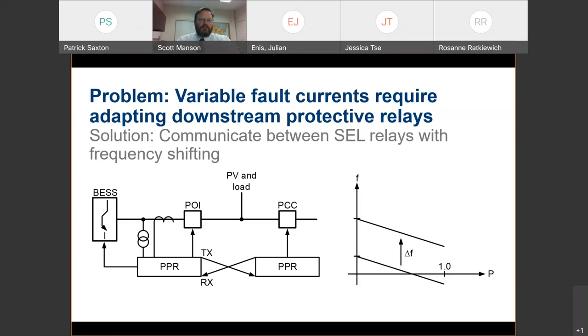Utility goes away and we have to shed some load, and now the inverter on a battery has to feed the load. That's in a typical use case, but perhaps it can only produce 2,000 amps. That is below the set point of, in fact, the relay settings, because they were set based upon a utility condition. So we have a contradiction, we have a problem. Because inverters can't produce those levels of currents needed, we need to adapt protection very quickly.